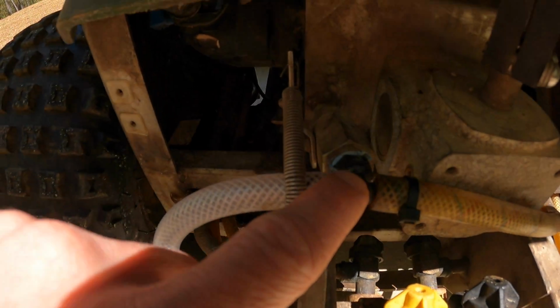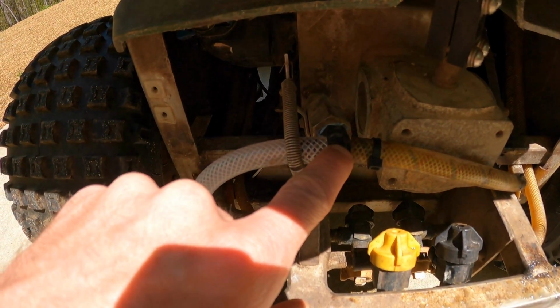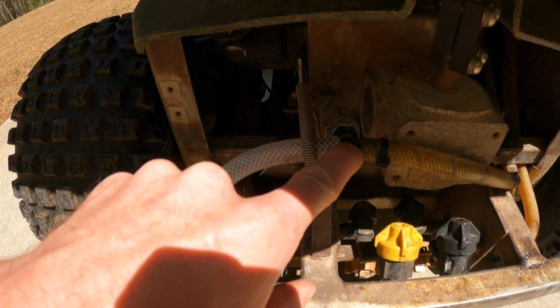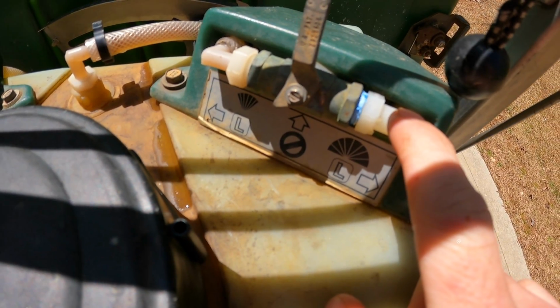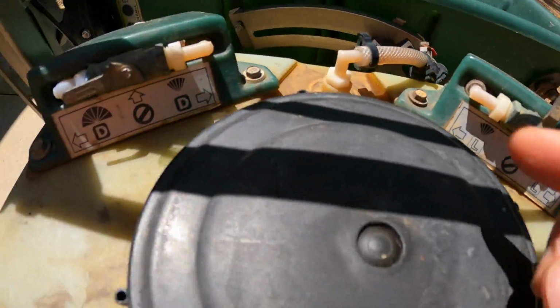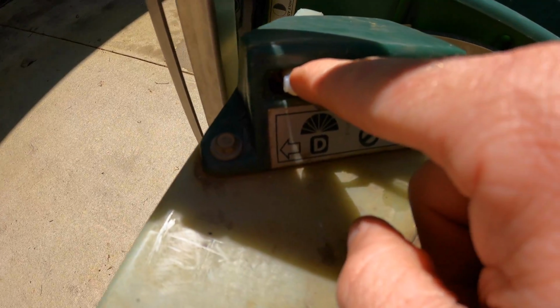Got an upgraded adapter here that takes it to the 3/8 inch line over the 1/4 inch line. These are new elbows that come into your valve. So all this has been upgraded to that larger line. So if you're going to attempt this with the factory 1/4 inch line that Permagreen gives you, it may or may not give you quite as high of a calibration.